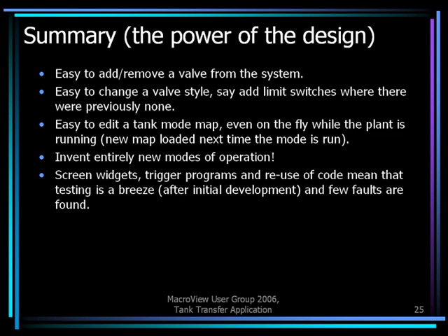Just wrapping up, a summary, the power of the design, I'll call that. We said we can easily add and remove a valve from the system. We can easily change a valve style, say adding limit switches, taking them away. Hopefully we won't be taking them away, hopefully we'll only be adding them. It's easy to edit a tank mode map, even on the fly while the plant's running.